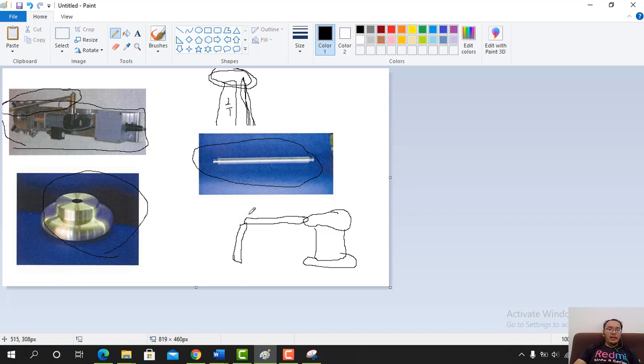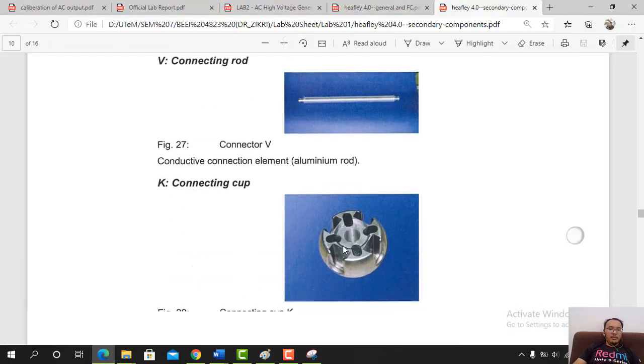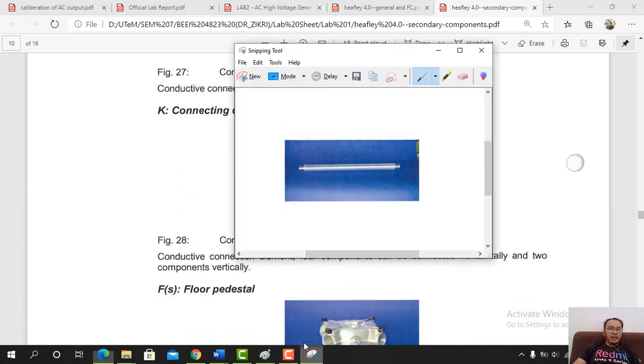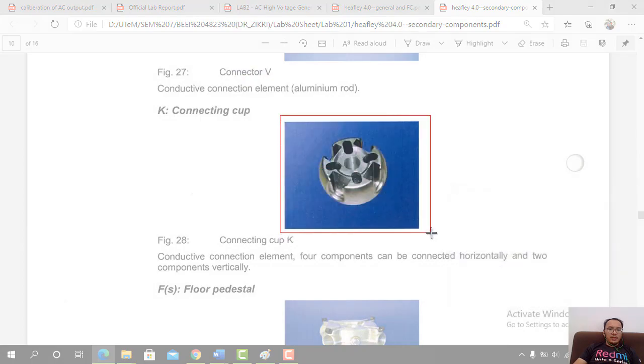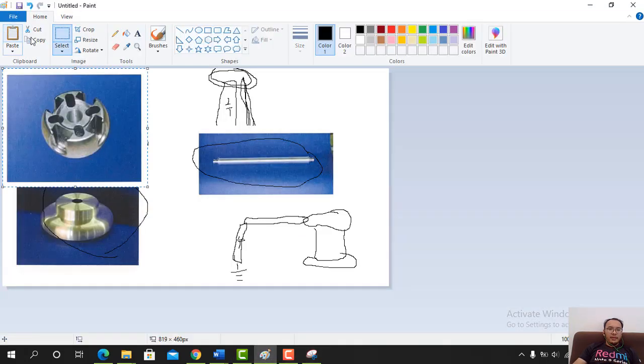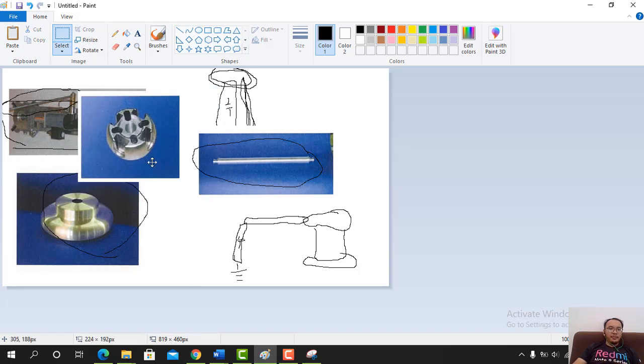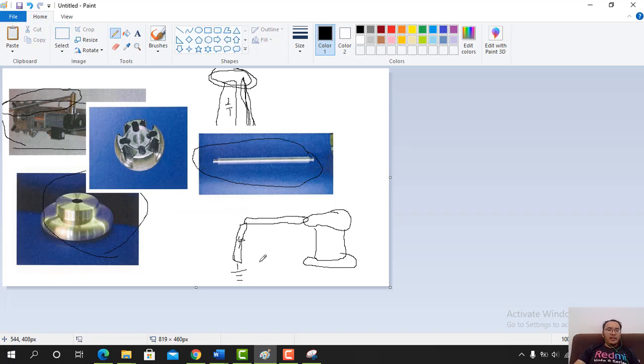In order to connect between the connection rod and our measuring capacitor, we use the connection cup. So this is our connection cup. I'll copy and paste it here. As I said before, the function of this connection cup is to connect between the test transformer and our connection rod, so it will be placed like here.